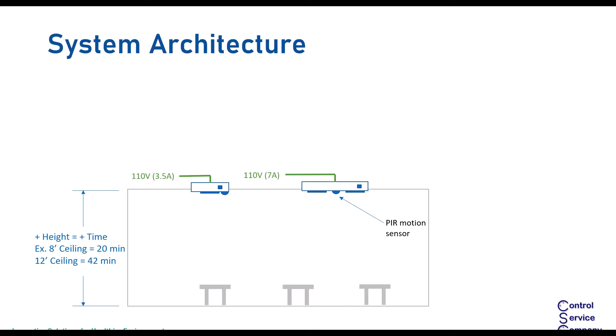Once powered, the next piece is that everyone has a building network. You may have a network that's everything, or your own isolated building network, but there's a network there for your building automation system to live on. Each of these fixtures is BACnet over IP, so you plug in Cat5, go back to your switch, and we assign a static IP address. We believe, like the rest of our equipment, static is much better. With DHCP you can lose leases and lose communication, and it's just more work, so we always recommend static IP addresses for these situations.